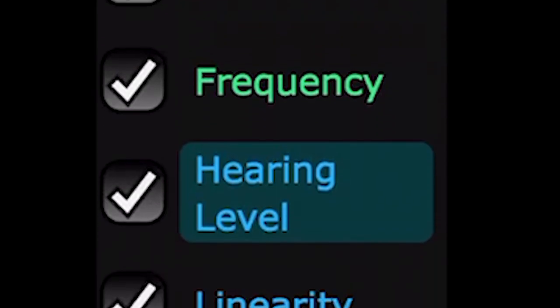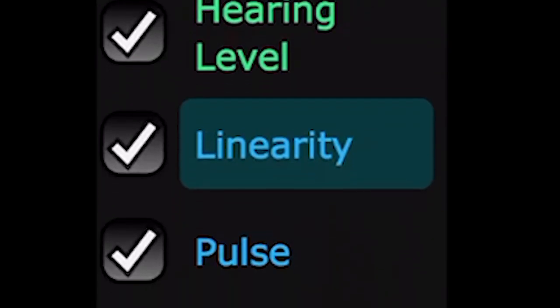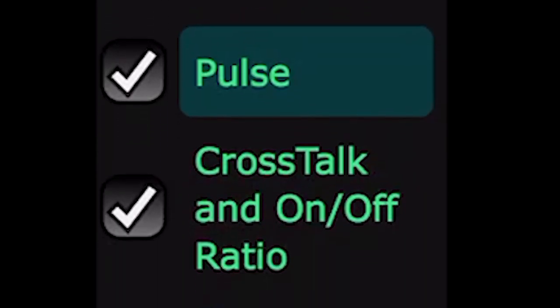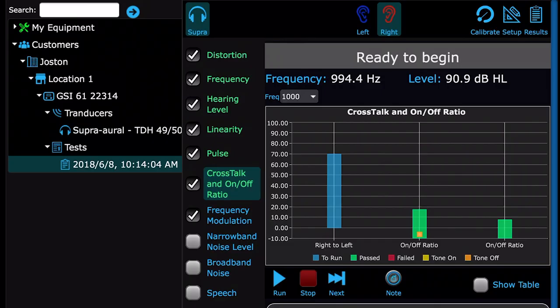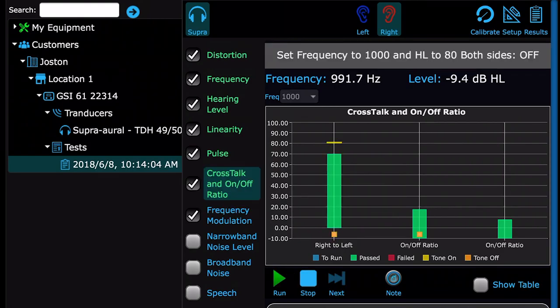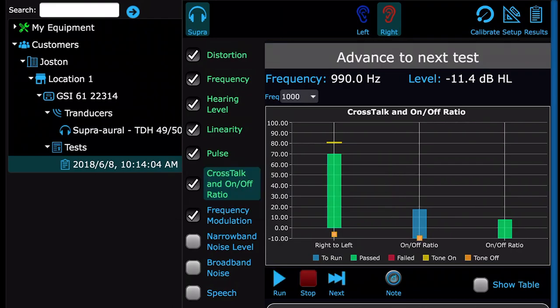The tests will turn from blue to green if passed, or red if any portion of the test has failed. Crosstalk finishes on this side — press Run, follow the prompt, press OK. You can choose to stop the test here or run the other two steps again.